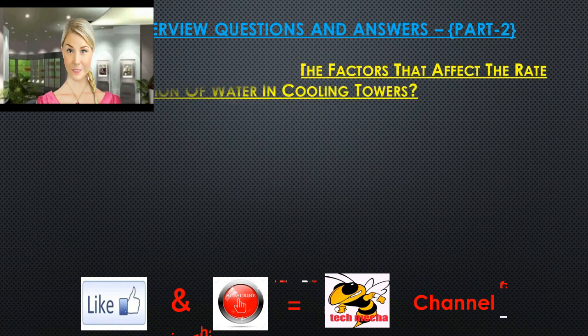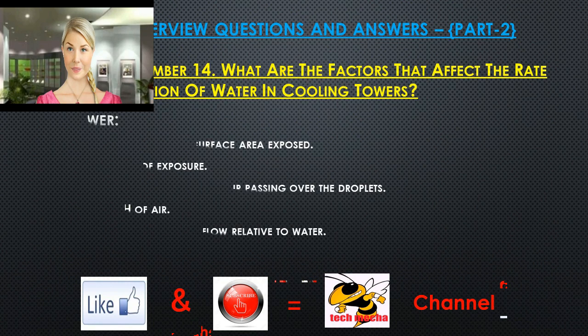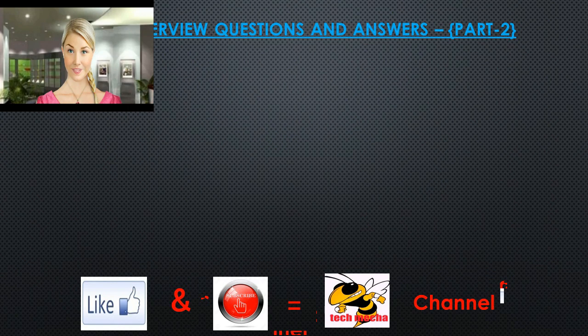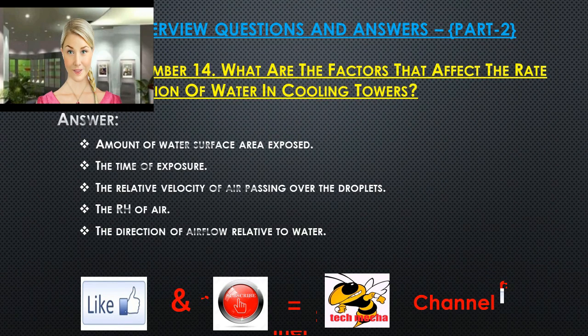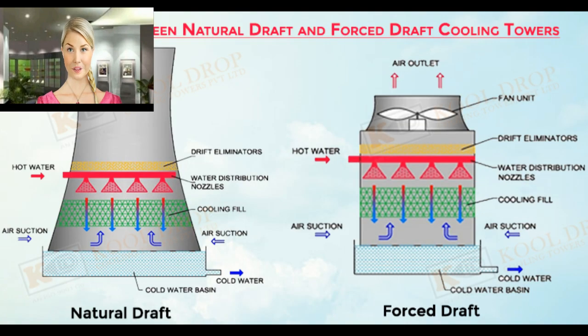Question 14: What are the factors that affect the rate of evaporation of water in cooling towers? The factors are: the amount of water surface area exposed, the time of exposure, the relative velocity of air passing over the droplets, the relative humidity of the air, and the direction of air flow relative to water.